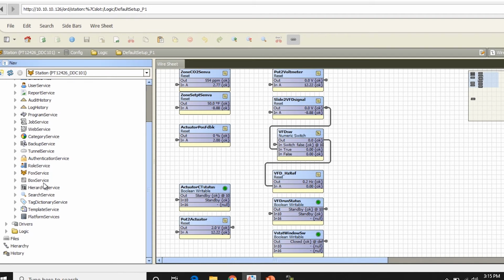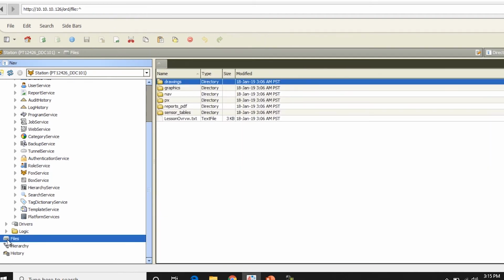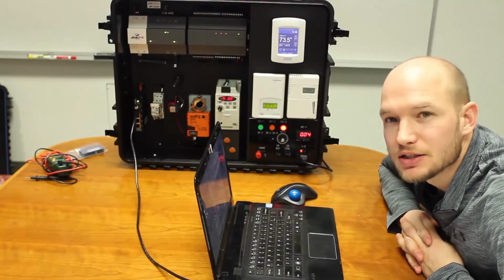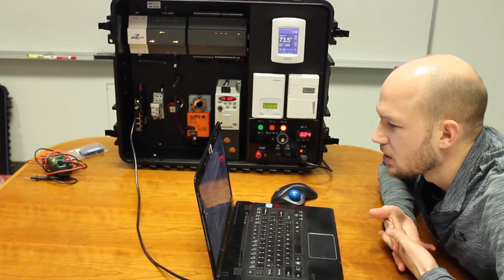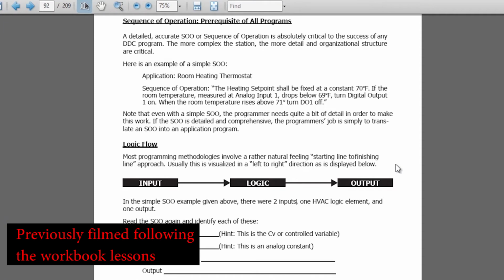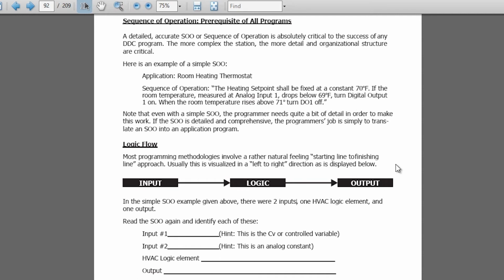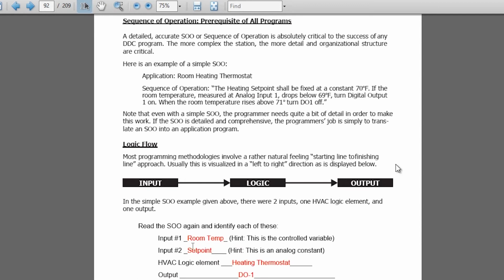Next thing I want to look at is the files folder, and a sequence of operation. Here we have a basic sequence of operation. The heating set point is at 70. If it drops below 69, we turn digital output 1 on. If it rises above 71, digital output 1 turns off. Input number 1 is the room temperature, input number 2 is the set point. The logic is the heating thermostat, and the output is digital output 1.